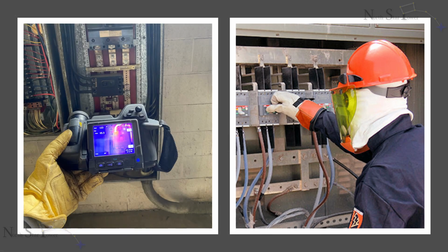Not all breakers have every function, but it is imperative that all elements are thoroughly tested. A delayed trip, as we have thoroughly emphasized, risks equipment damage, shock hazards, fires, arc flash, downtime, and OSHA fines. Premature tripping can also shut down systems unnecessarily, leading to expensive downtime and untrained personnel tampering with settings.